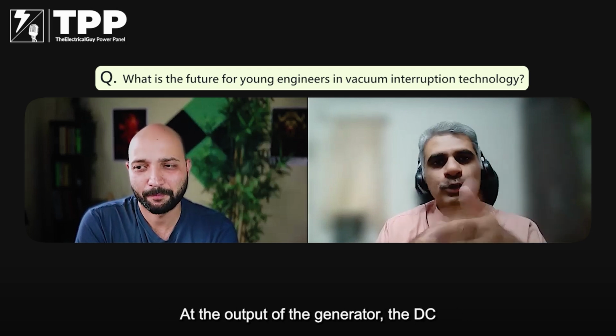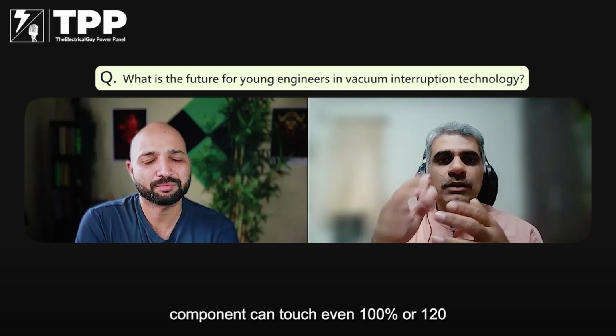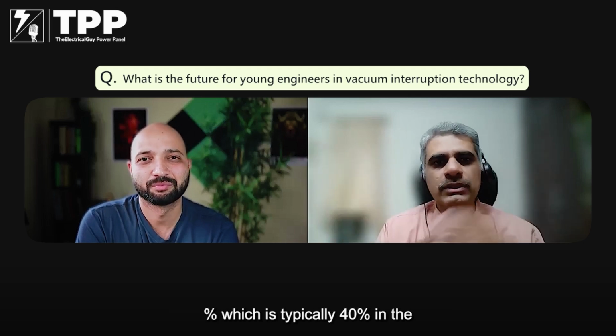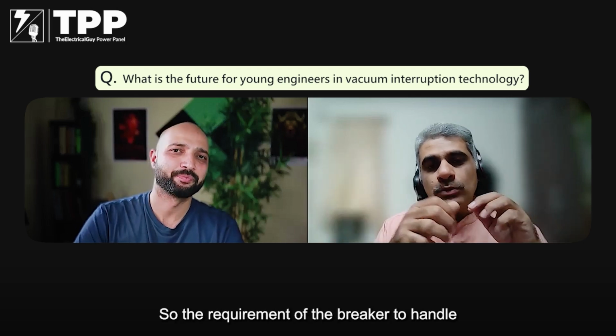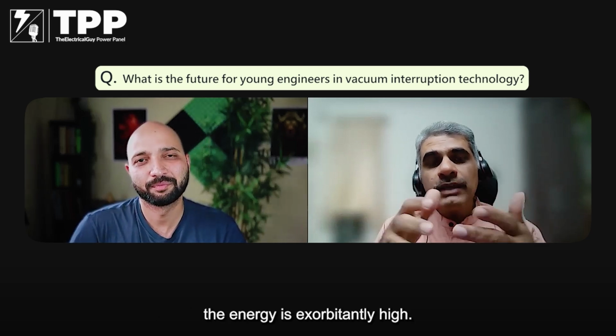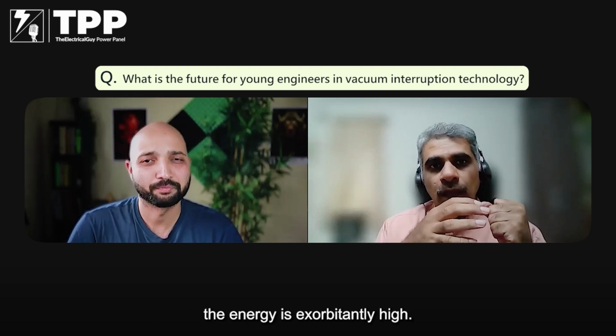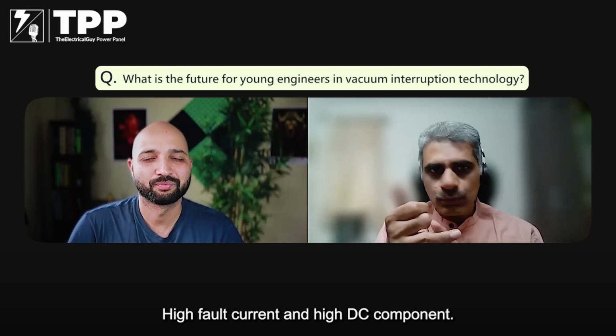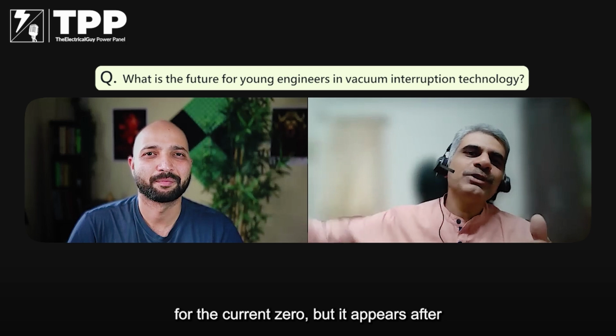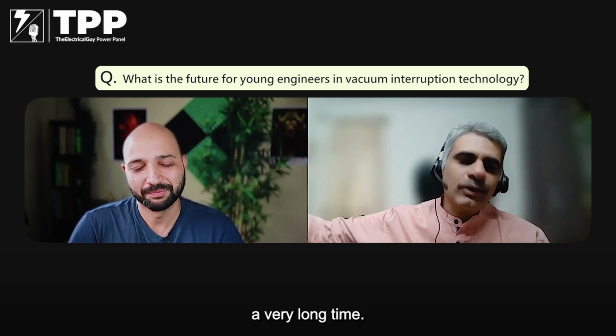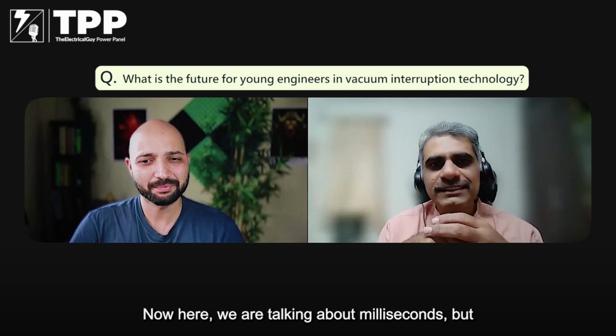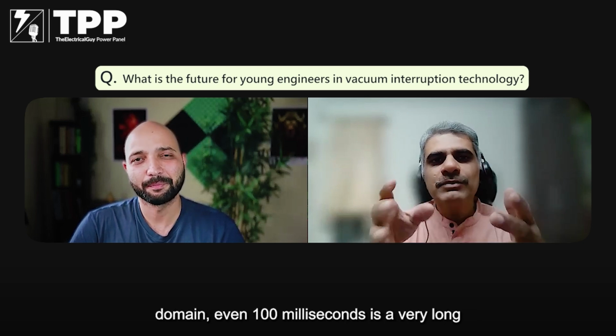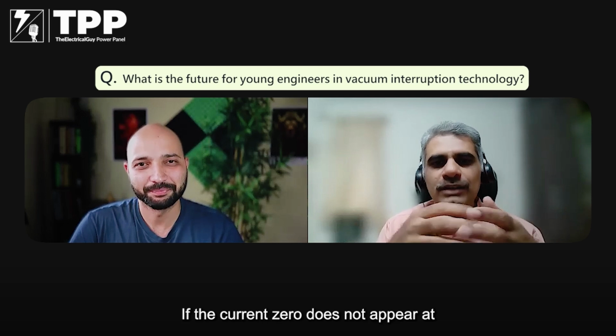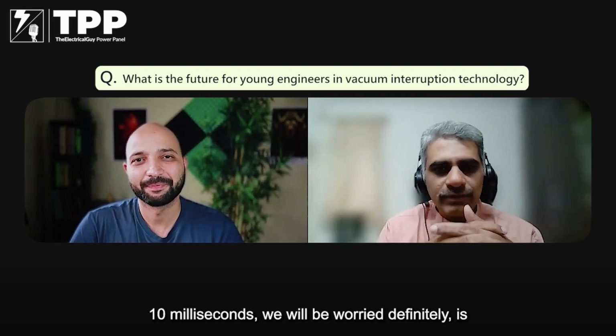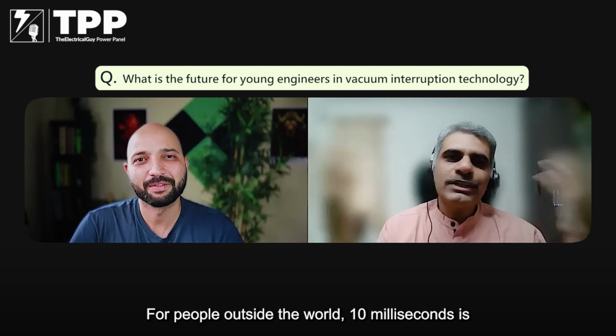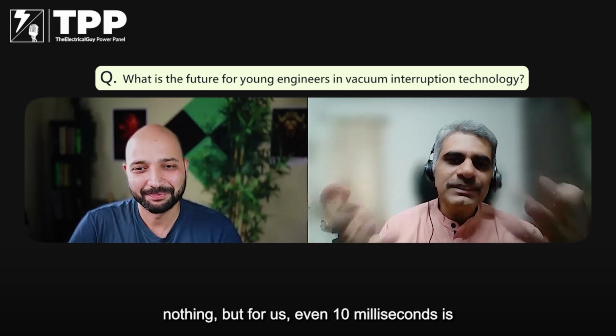At the output of the generator, the DC component can touch even 100% or 120%, which is typically 40% in the distribution class breakers. So the requirement of the breaker to handle the energy is exorbitantly high: high fault current and high DC component. The breaker keeps on waiting for the current zero, but it appears after a very long time. Now here we are talking about milliseconds, but for us engineers who are working in this domain, even 100 milliseconds is a very long time, isn't it? If a current zero does not appear at 10 milliseconds, we will be worried, definitely. For people outside the world, 10 milliseconds is nothing, but for us, even 10 milliseconds is everything.